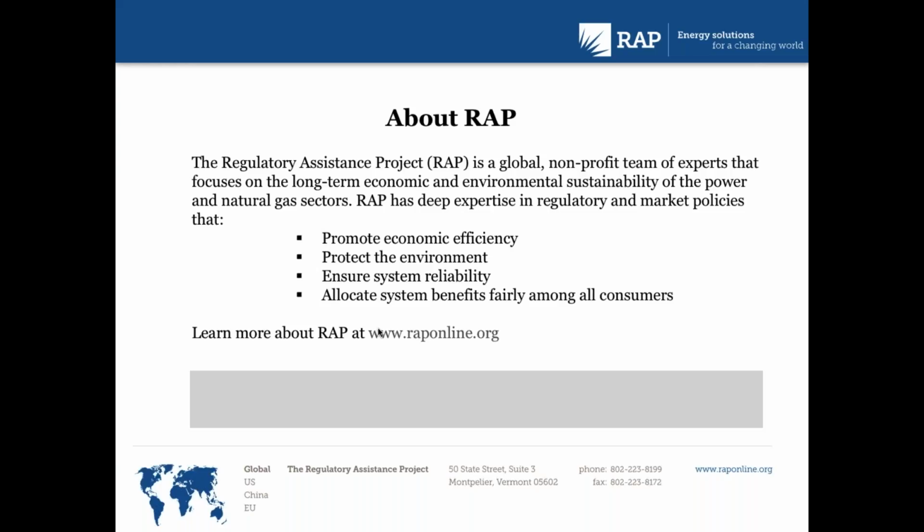new power plant. And I can give you a concrete example of a plant that I had down in the Houston Ship Channel a number of years ago. Now, this is in the ERCOT market, so we're talking about the responsive reserves product, or the spinning reserves product. This was an 800 megawatt gas-fired combined cycle plant, providing steam to a petrochemical facility. And with a $5 million investment, we were able to boost the amount of responsive reserve we could provide to the ERCOT market by a considerable amount, much more cheaply than it would have cost for some of the alternatives. It would have required a new greenfield investment, and that's the right market solution. Anyway, that's a long-winded answer to that question.